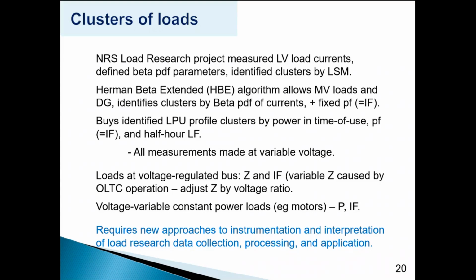But then there are some things, motors are power devices, and others truly are impedances. So the Load Research Project took the sort of happy middle in measuring currents, and that was very deliberate. It was the input to the Herman-Beta algorithm, to the Herman-Beta extended algorithm, which can be applied to MV loads and DG and includes loads which are not at unity power factor and systems which are not defined only by the resistance. So for that sort of application, you need to identify clusters by the beta PDF of currents and a fixed PDF, fixed power factor, or the impedance factor.